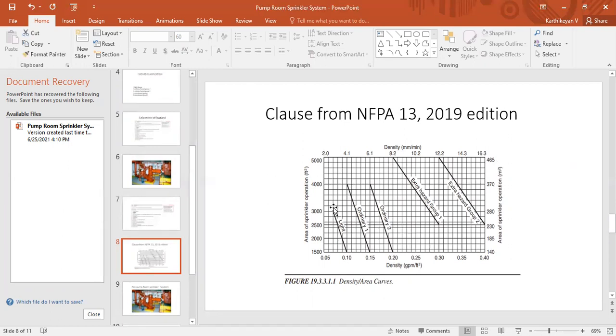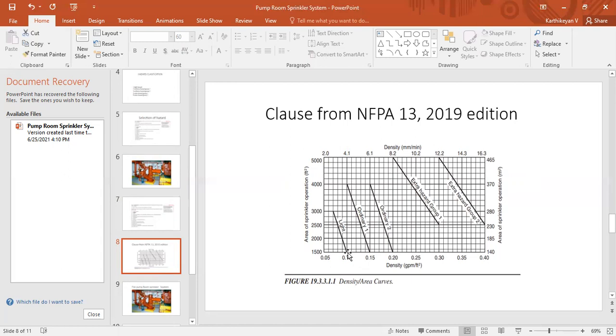All the hazard curves are available here. Once you complete the hazard classification you need to select with a single point selection. If your hazard is light hazard, through this curve you have to select any one point. If I'm selecting here the starting point, my design density will be 4.1 lpm and my design area will be 139 square meters. It starts at 140 square meters. Like that we have to select.